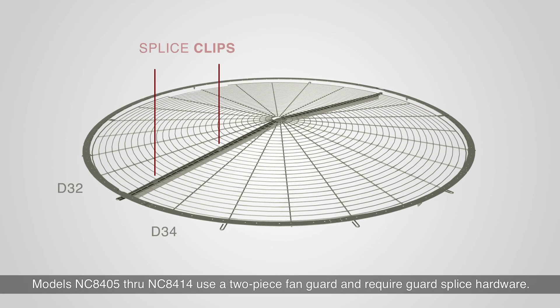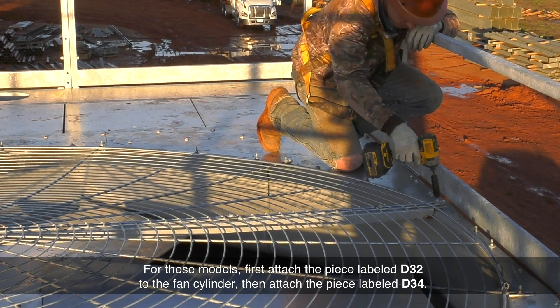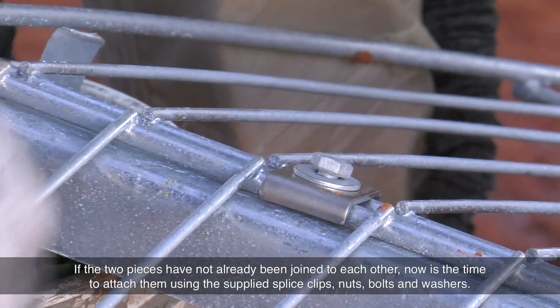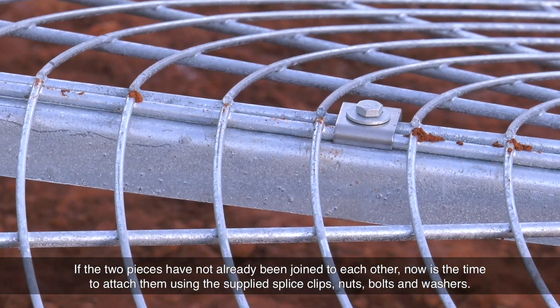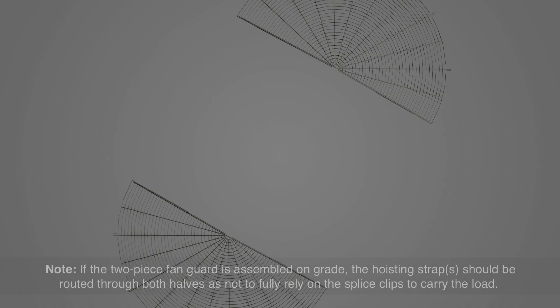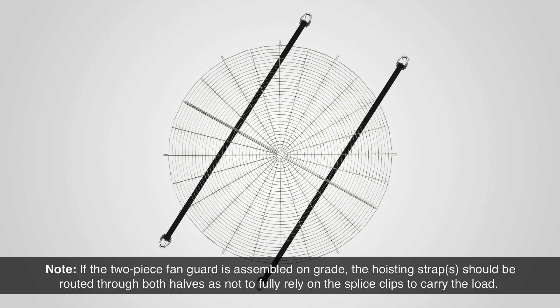Models NC8405 through NC8414 use a two-piece fan guard and require guard splice hardware. For these models, first attach the piece labeled D32 to the fan cylinder, then attach the piece labeled D34. If the two pieces have not already been joined to each other, now is the time to attach them using the supplied splice clips, nuts, bolts, and washers. If the two-piece fan guard is assembled on grade, the hoisting strap should be routed through both halves so as to not fully rely on the splice clips to carry the load.